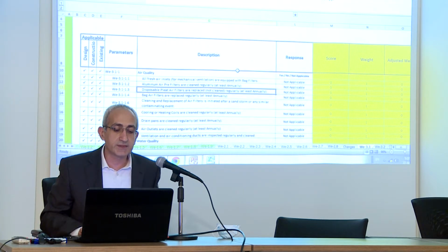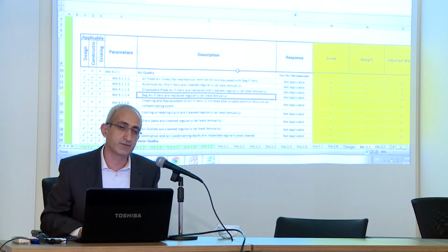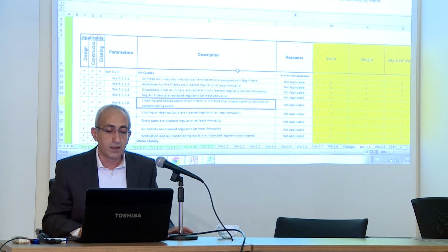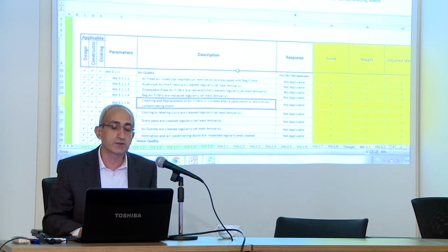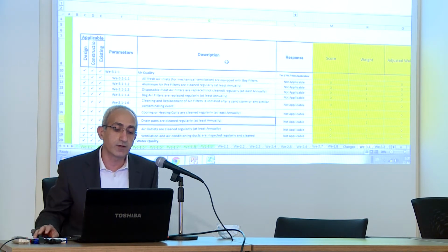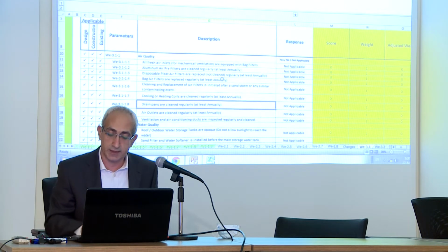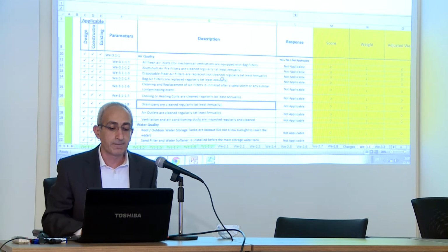Disposable pleated air filters are replaced and not cleaned. Bag filters are replaced and not cleaned. I have seen teams cleaning back filters, which is not effective at all. Cleaning and replacement of air filters is initiated after a sandstorm or severe contaminating event. Cleaning of cooling and heating coils is regular and on an annual basis. Cleaning of drain pans is also regularly done, at least annually.